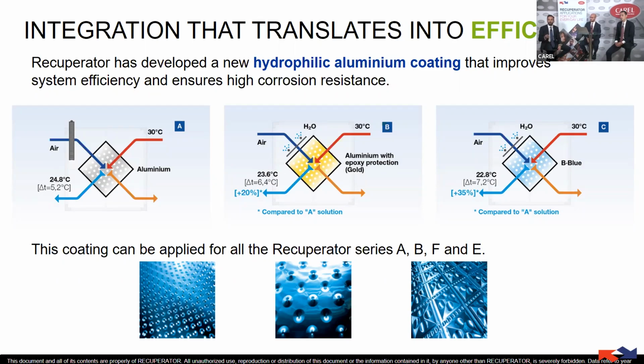In fact, with the first example, we reach 5.2 degrees of difference in terms of temperature between inlet and outlet of the supply air. In the second case, if we replace the wet pad with the pressurized system, we can have a 20% increase of cooling capacity, and we can go even further thanks to the blue coating, this hydrophilic aluminium coating, which increases the cooling capacity up to 35% compared to the first solution. So let's say again: pressurized system, humidification at the inlet, and the plate exchanger should be completely wet. This coating can, of course, be applied to the whole range of heat exchangers in the Recuperator portfolio.